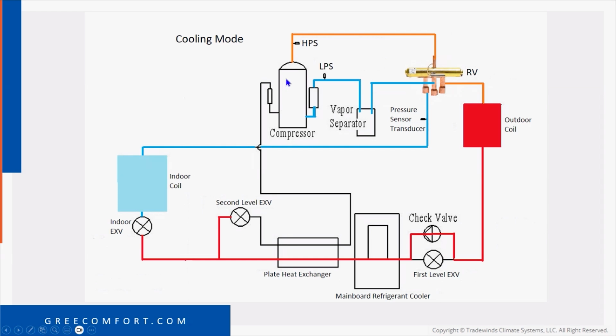When you follow the flow, you follow it from the compressor. So you've got your discharge gas coming off, we go into our reversing valve. Obviously, we're in cooling mode. We're discharging to our outdoor unit, releasing the heat, condensing into a liquid. Then we are going around the EEV outside. I think it's actually going through both. I would tell you this because this EEV is going to go wide open when it's in cooling mode. So I think you actually have liquid refrigerant flowing through both, but I just highlighted the diagram that way to show you what's going on.